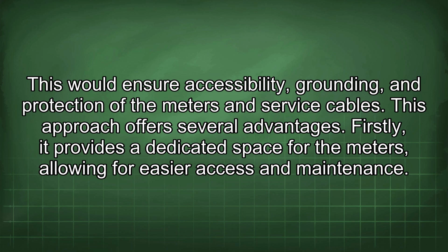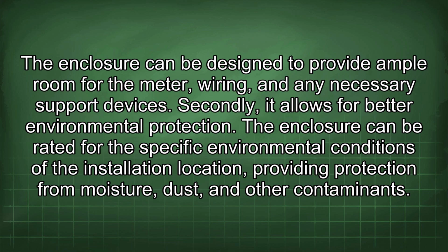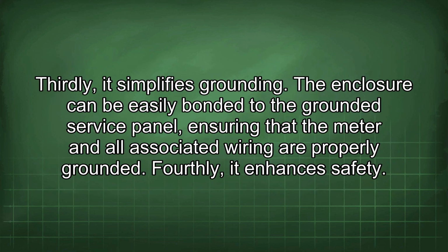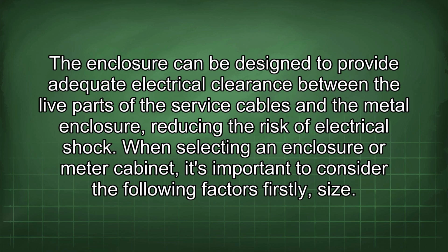This approach offers several advantages. Firstly, it provides a dedicated space for the meters, allowing for easier access and maintenance. The enclosure can be designed to provide ample room for the meter, wiring, and any necessary support devices. Secondly, it allows for better environmental protection. The enclosure can be rated for the specific environmental conditions of the installation location, providing protection from moisture, dust, and other contaminants. Thirdly, it simplifies grounding. The enclosure can be easily bonded to the grounded service panel, ensuring that the meter and all associated wiring are properly grounded. Fourthly, it enhances safety. The enclosure can be designed to provide adequate electrical clearance between the live parts of the service cables and the metal enclosure, reducing the risk of electrical shock.